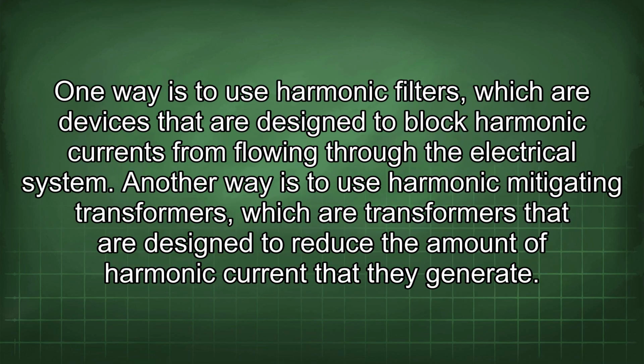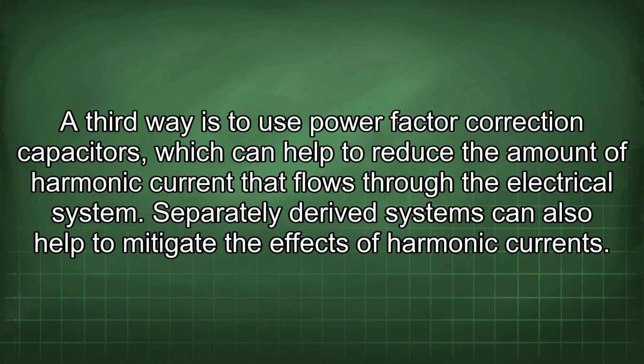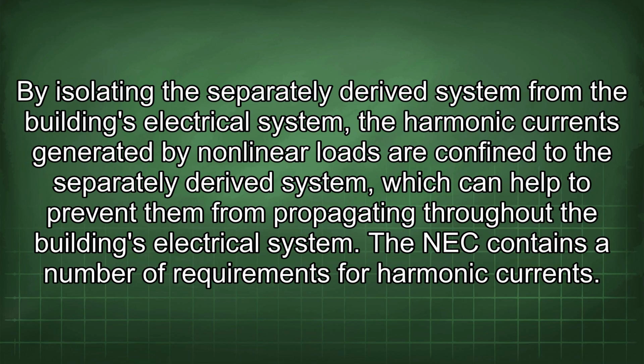There are a number of ways to mitigate the effects of harmonic currents. One way is to use harmonic filters, which are devices that are designed to block harmonic currents from flowing through the electrical system. Another way is to use harmonic mitigating transformers, which are transformers that are designed to reduce the amount of harmonic current that they generate. A third way is to use power factor correction capacitors, which can help to reduce the amount of harmonic current that flows through the electrical system. Separately derived systems can also help to mitigate the effects of harmonic currents. By isolating the separately derived system from the building's electrical system, the harmonic currents generated by nonlinear loads are confined to the separately derived system, which can help to prevent them from propagating throughout the building's electrical system.